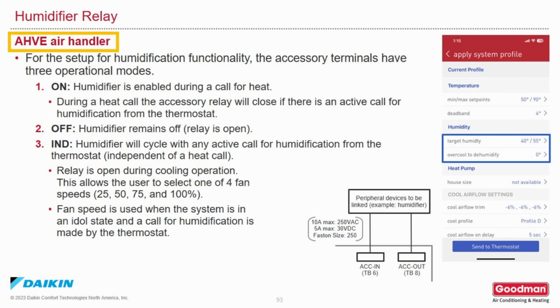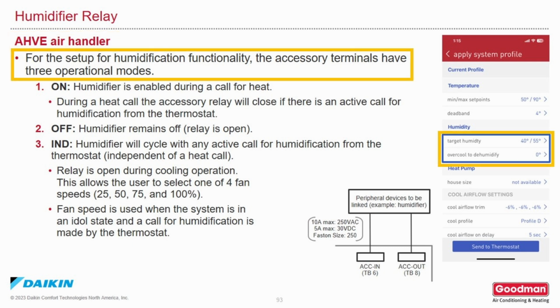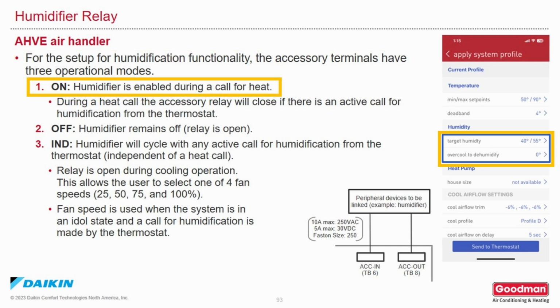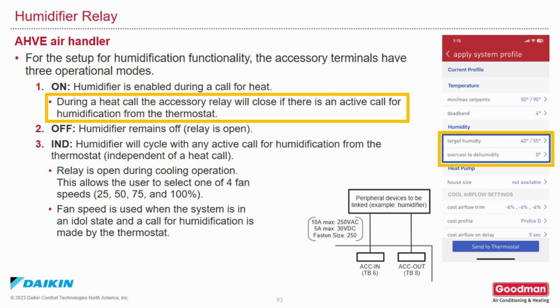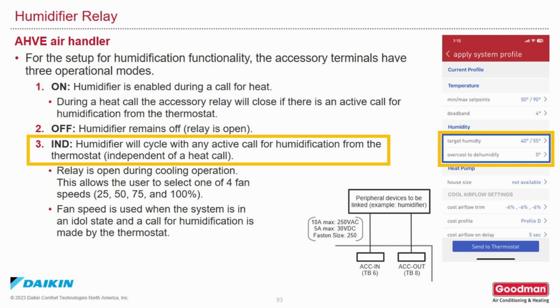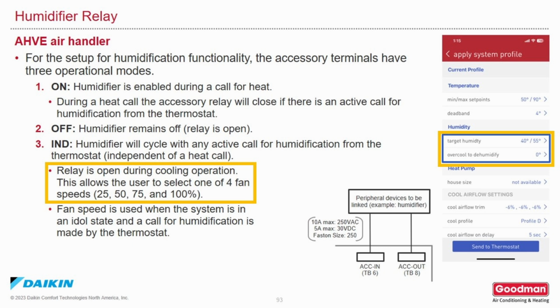Humidity control using the AHVE air handler. For the setup for humidification functionality, the accessory terminals have 3 operational modes. Number 1, on: the humidifier will be enabled during a call for heat. That means that during any call for heat, the accessory relay will close if there is an active call for humidification from the thermostat. Number 2, off: the humidifier remains off and the relay is open. Number 3, independent: the humidifier will cycle with any active call for humidification from the thermostat that's independent from a call for heat. The relay will open during cooling operation.